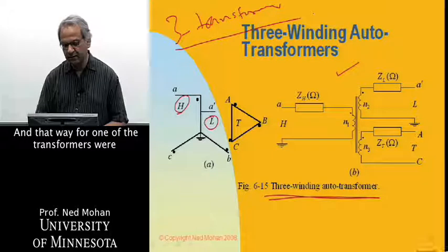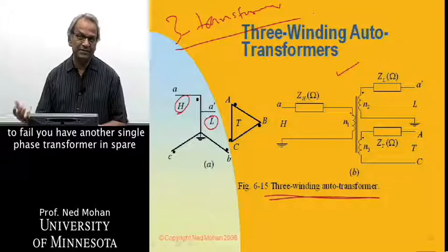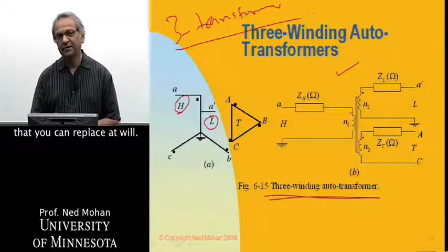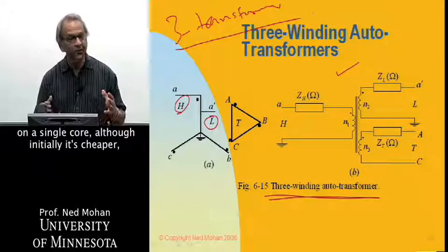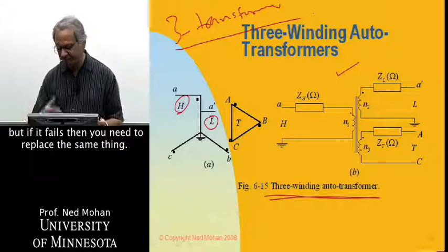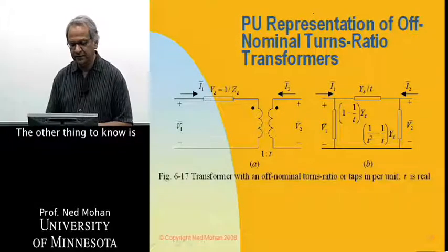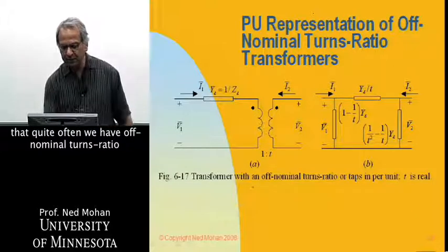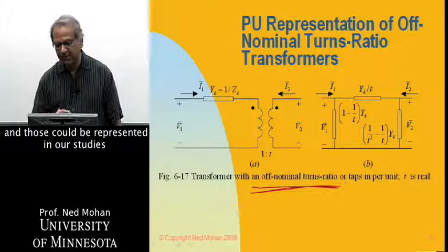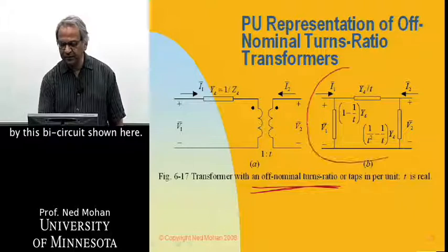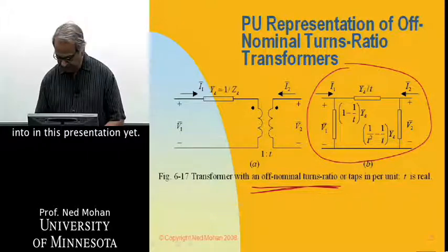And that way, if one of the transformers were to fail, you have another single-phase transformer in spare, which you can replace it with. But if you're using a three-phase transformer where everything is on a single core, although initially it's cheaper, but if it fails, then you need to replace the whole thing. So there are pros and cons. The other thing we have to know is that quite often we have off-nominal turns ratios, and those could be represented in our studies by this pi circuit shown here. And again, that is the detail that I will not go into in this presentation here.